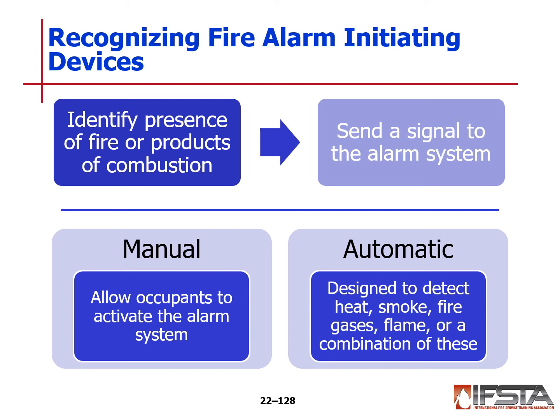Recognizing fire alarm initiating devices: we identify the presence of fire or products of combustion. So they're going to identify smoke or heat or the rate of rise of heat, and then send a signal to the alarm system or the alarm panel. Manual can allow occupants to activate the system, such as pull devices, one of the most common. Automatic would be designed to detect products of combustion, such as heat, smoke, fire gases, flame, or a combination of these.